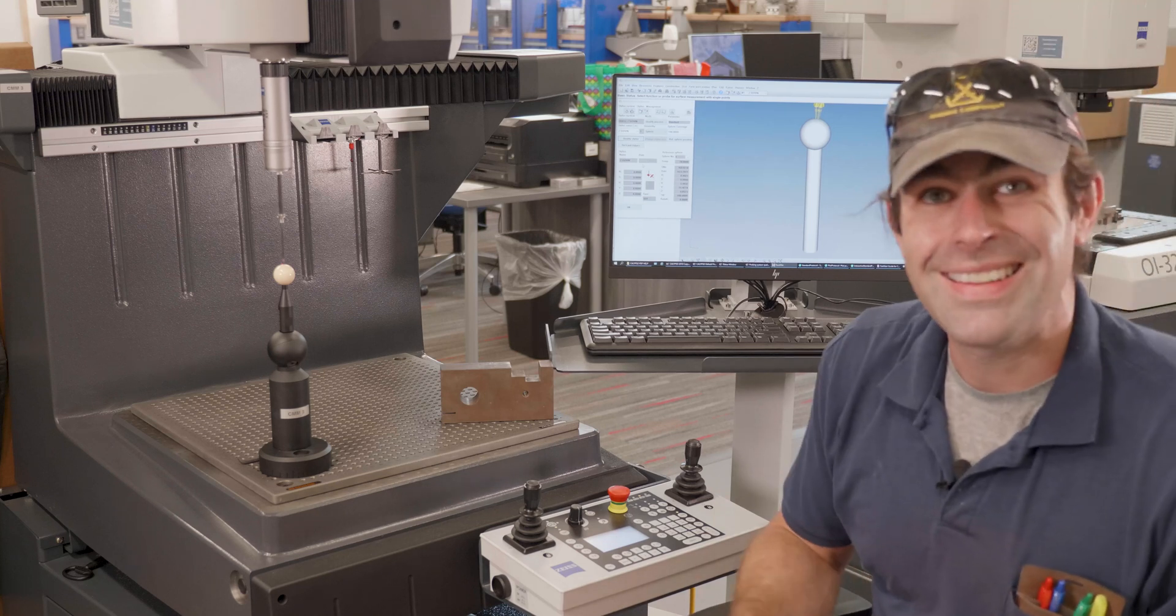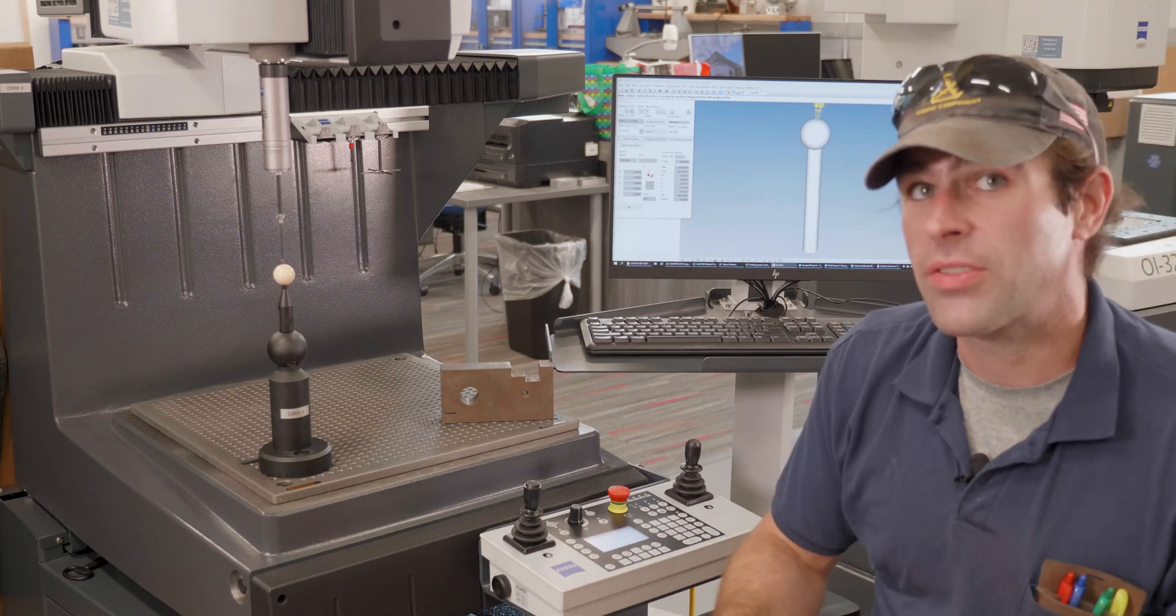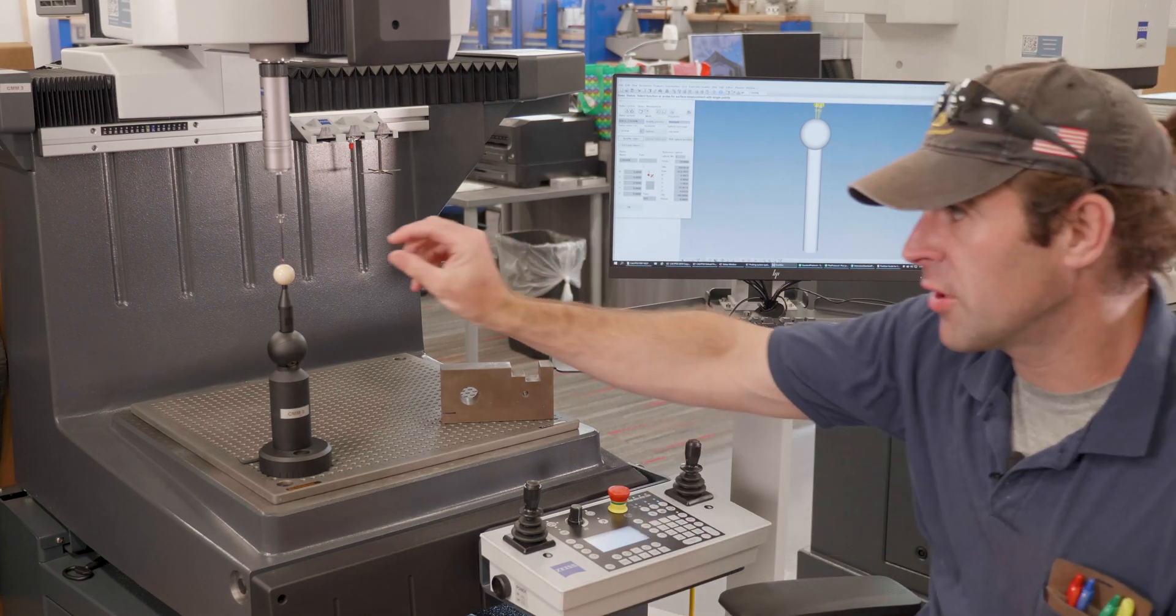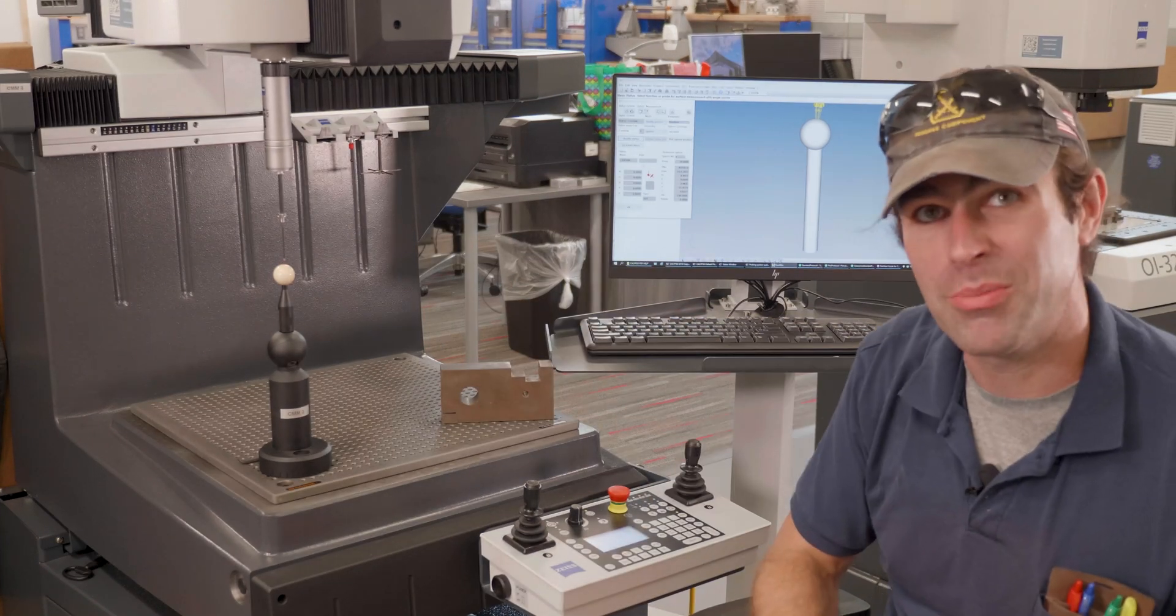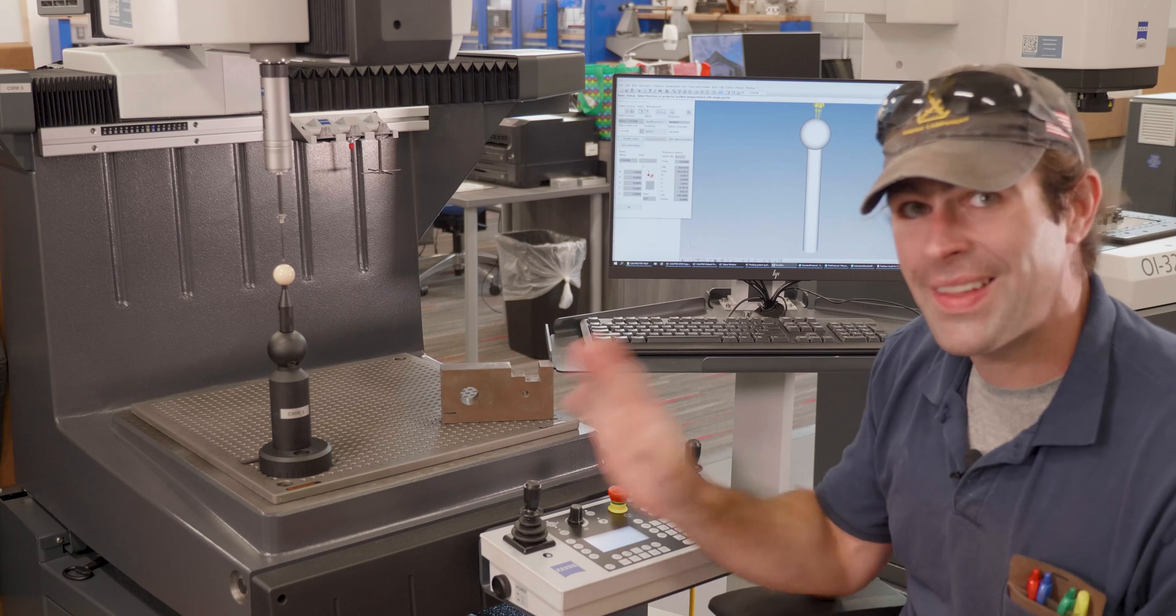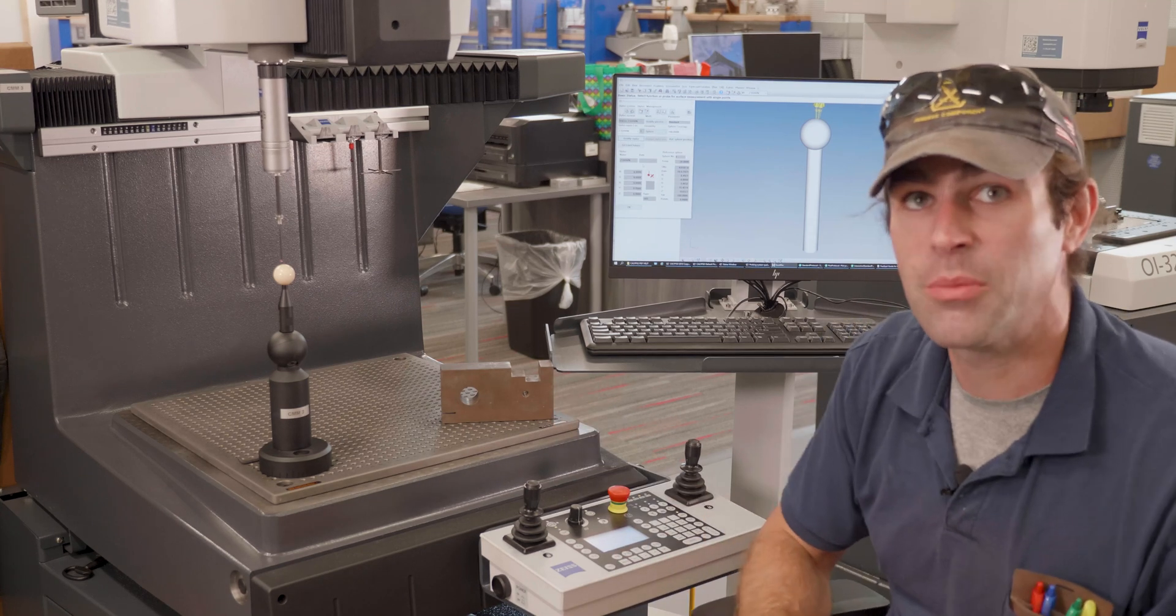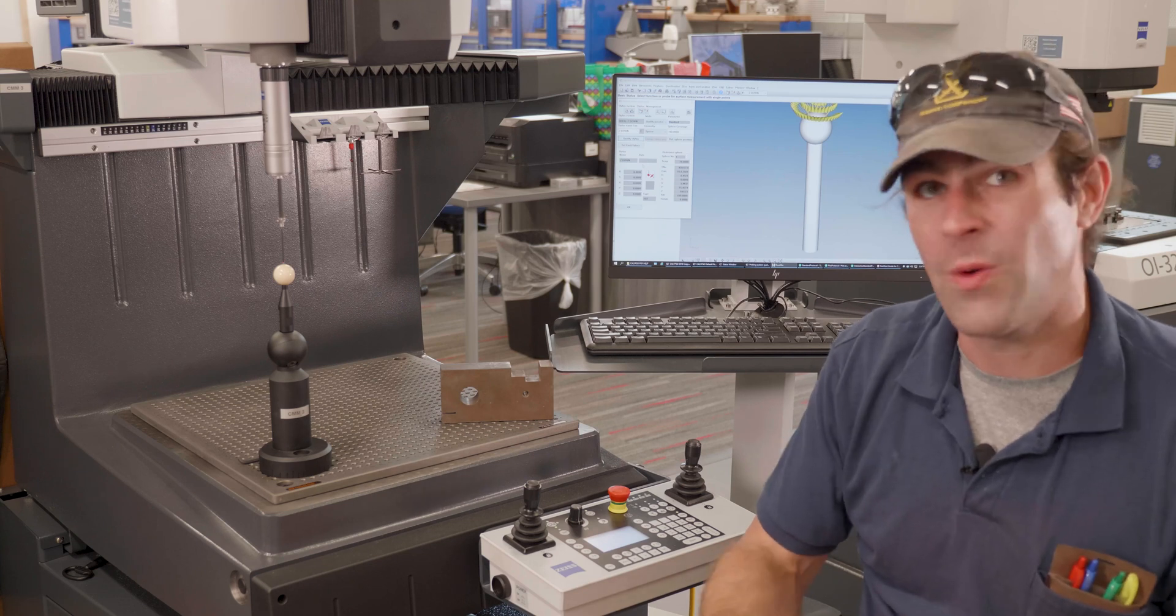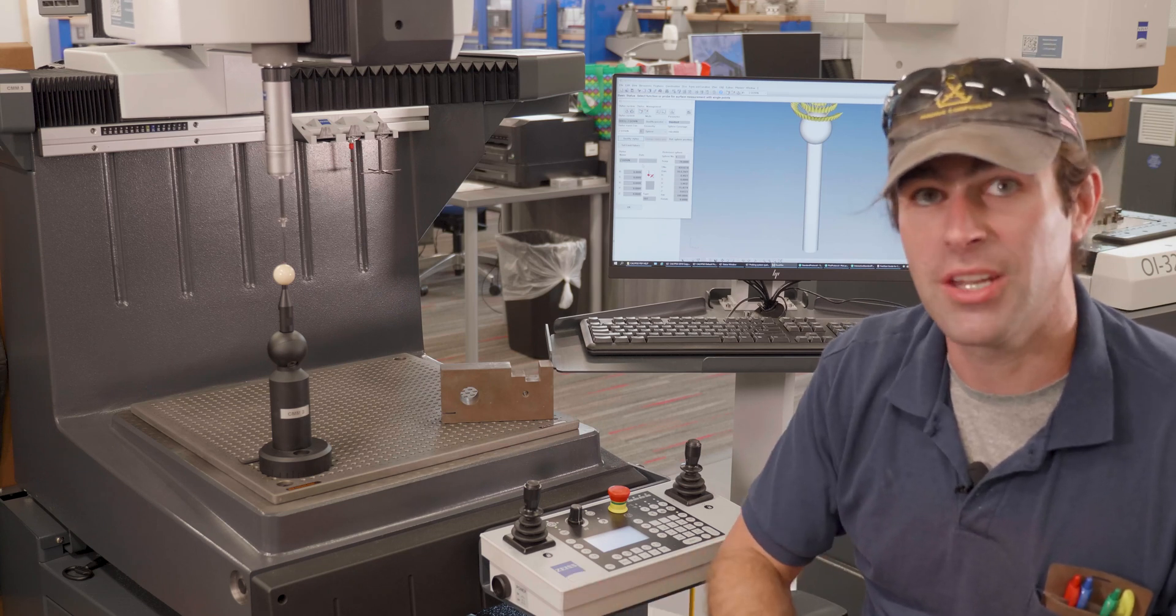Now the machine is on autopilot. It's going to scan that reference sphere, and when it's done it'll finish. It'll leave the probe about a half inch above that reference sphere, and that stylus system will be qualified. You could write a program for a part right then and there and check something if you needed to.